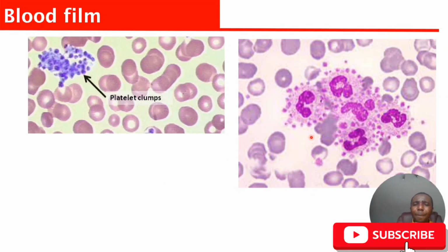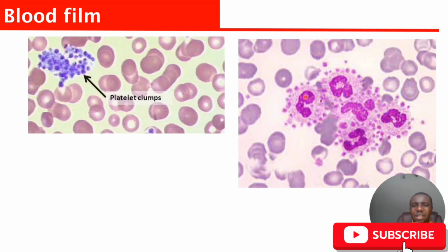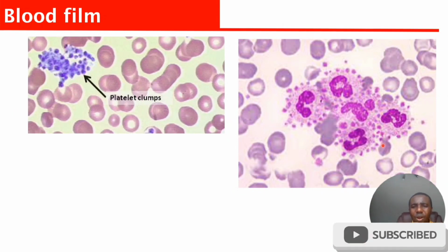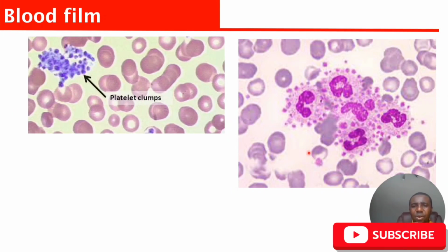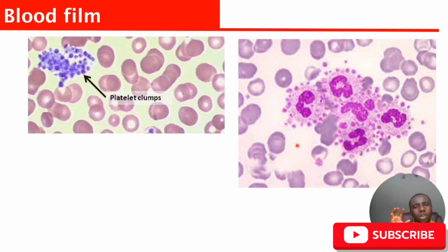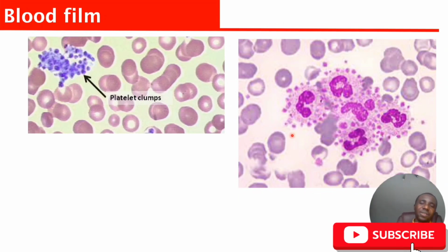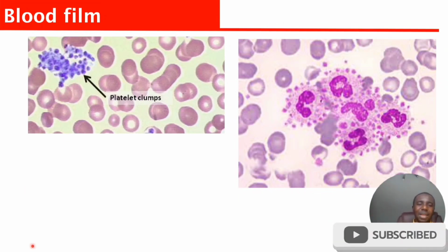Now, I also mentioned platelet satellitism. This is what I mean by platelet satellitism. You can see that these are neutrophils, and on the side of these neutrophils, you can see the platelets. So these are the platelets surrounding these neutrophils. And due to this surrounding, when these neutrophils pass through the aperture, the platelets will also pass through that aperture without being counted, and that can lead to a low platelet count.